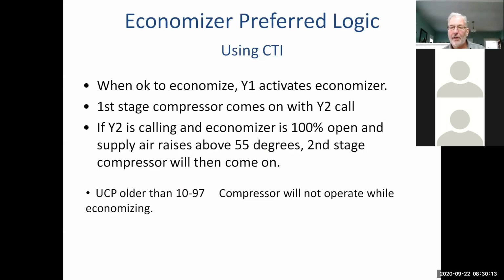So in other words, you could have a Y1 and a Y2 call, and it could be in economize and the compressor is not coming on just because the economizer needs to go to 100% open for at least 5 minutes, and we have to not maintain that 55 degrees. Then it will allow that compressor to come on at that point.